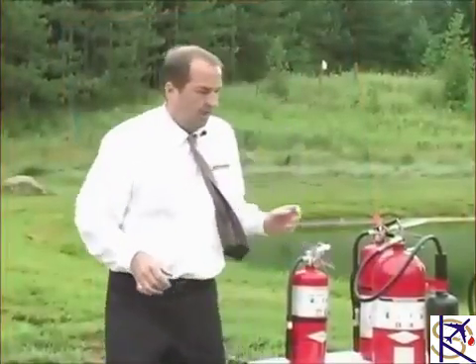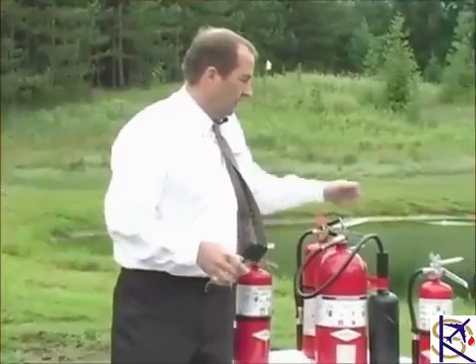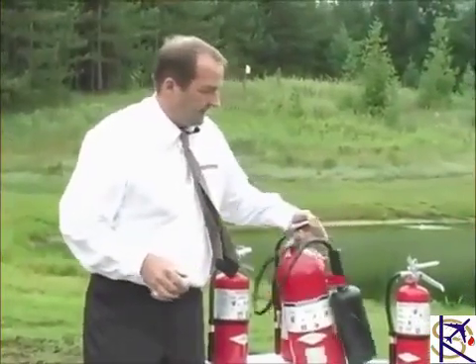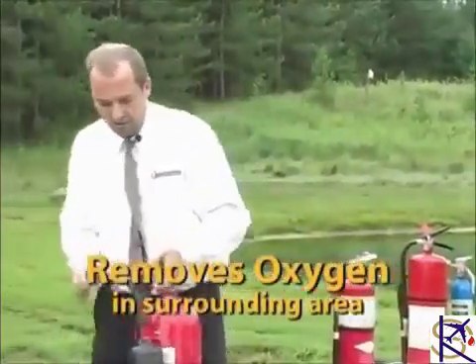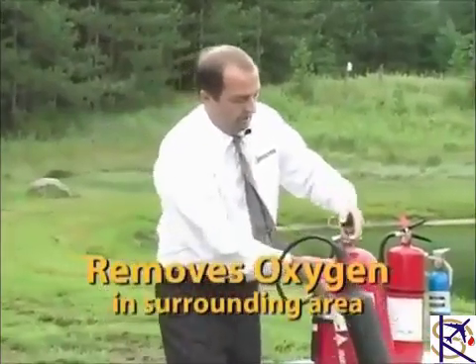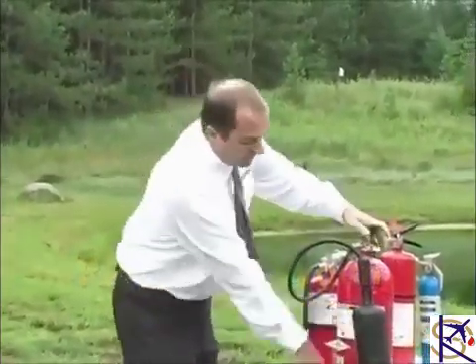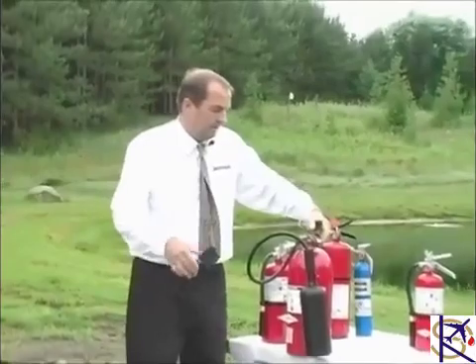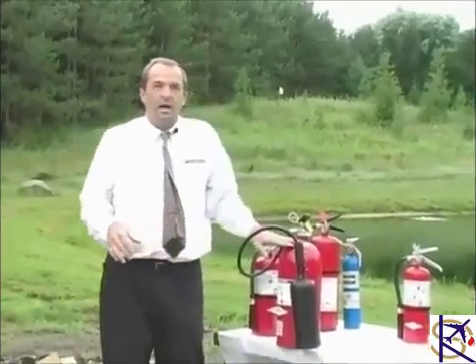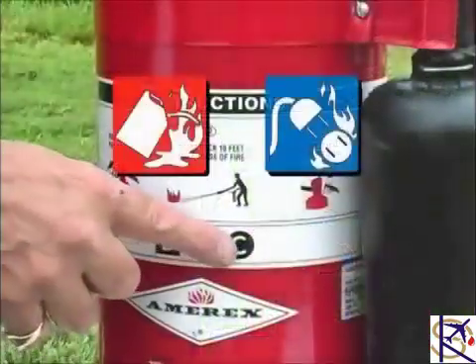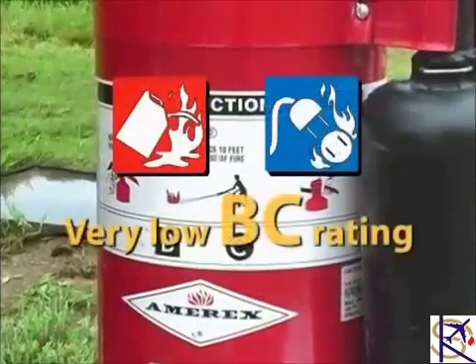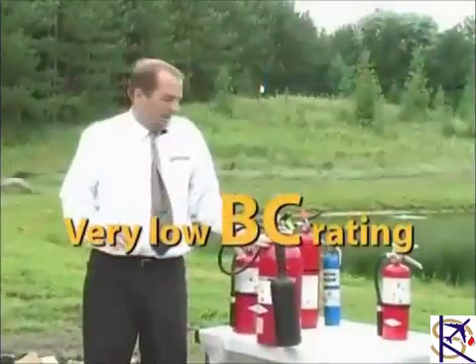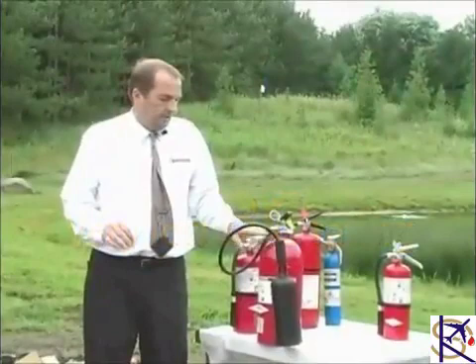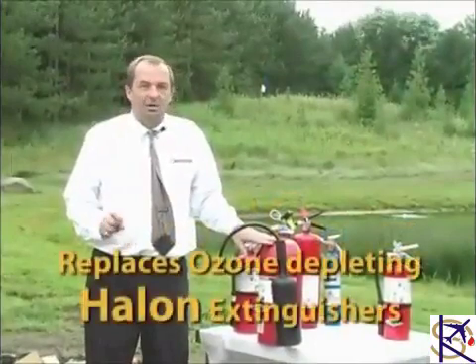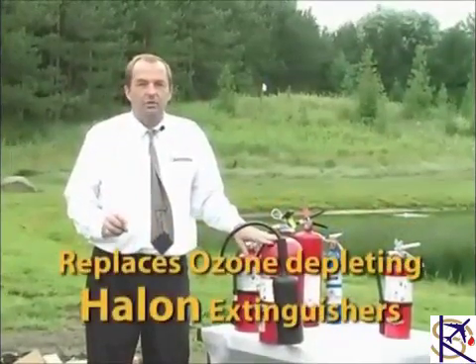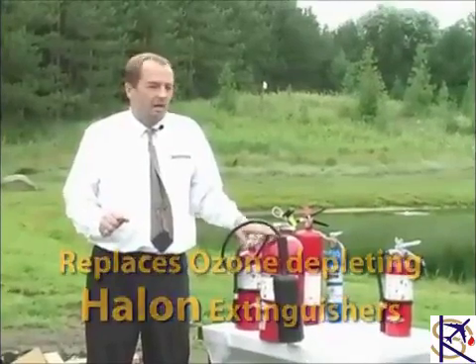Next, we'll talk about a CO2. CO2 basically removes the oxygen, and it cools the fire at the same time. It has no A rating, strictly B and C rating, but a very low B and C rating. It is used to replace the older halon extinguishers, which are ozone depleting.